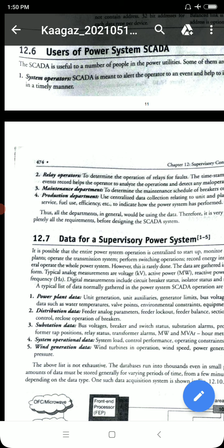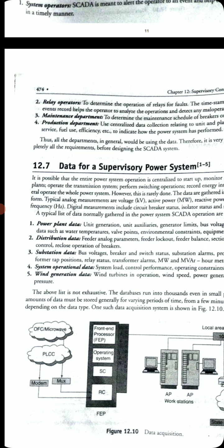Next, what is the data for the supervisory power system, or SCADA system? Till now we have said that data acquisition takes place, so what are the data that are acquired? The first one is the power plant data. Power plant data is unit generation, unit auxiliaries available, and generator limits. What is the limit of the generator, how much it can generate, that is the minimum and maximum generator limits. Then bus voltages, unit performance data such as water temperatures, valve points, environmental constraints, and equipment constraints. All these come under the power plant data.